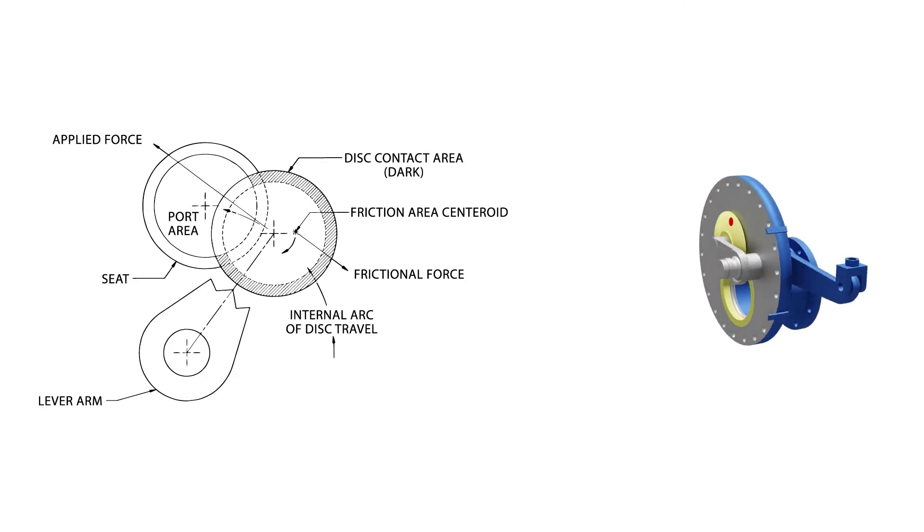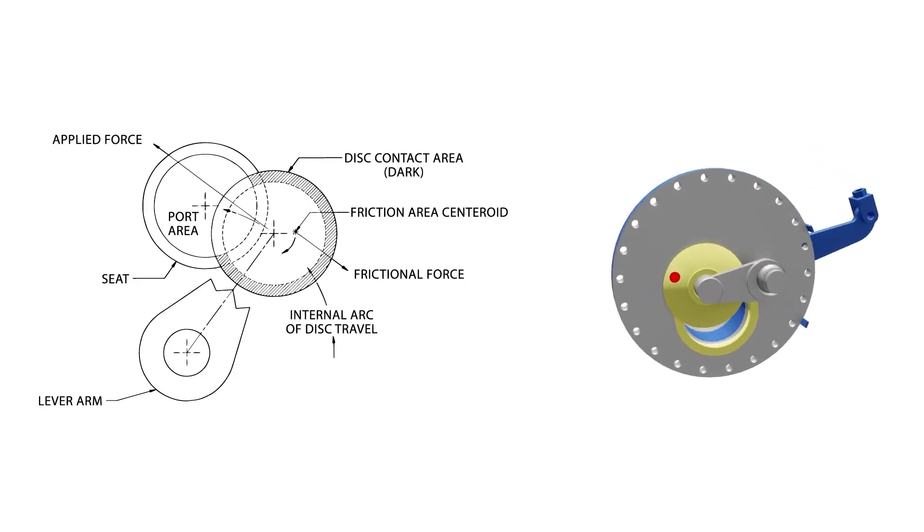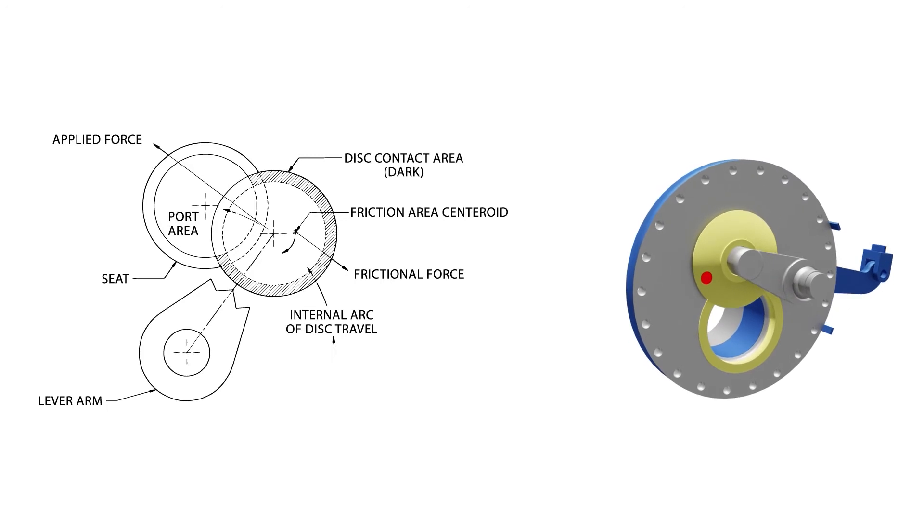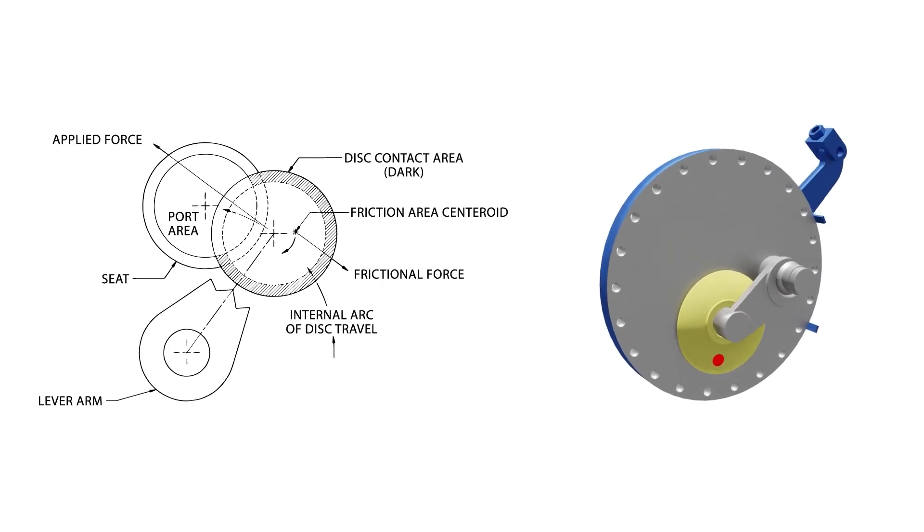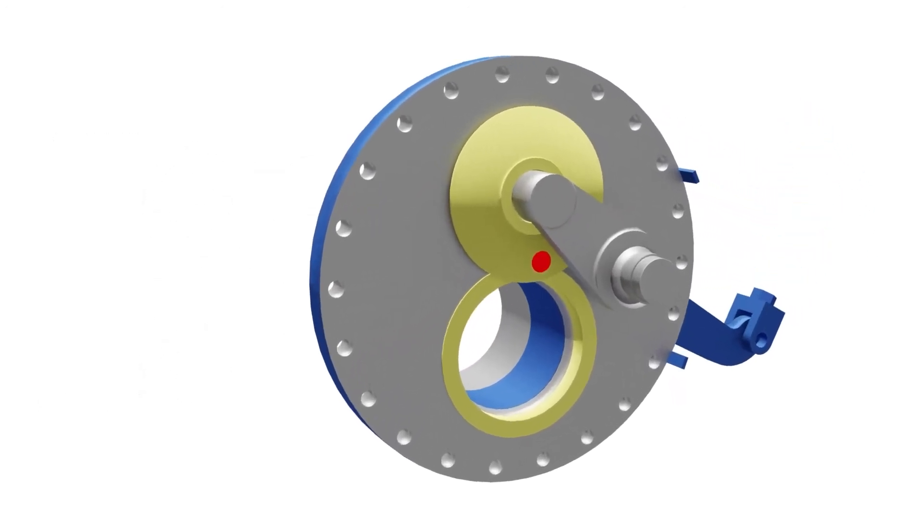but, over time, will lap the metal-to-metal seating surfaces. Hence, Everlasting's rotating disc valve will actually reduce its leak rate with use, even on the most abrasive solids.